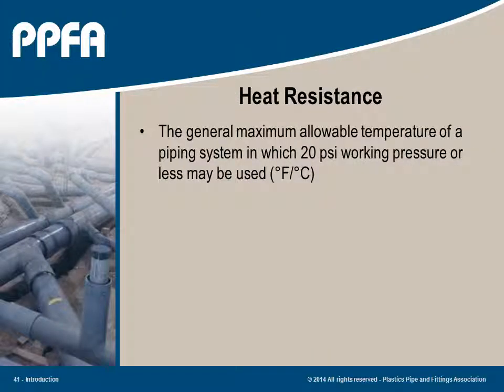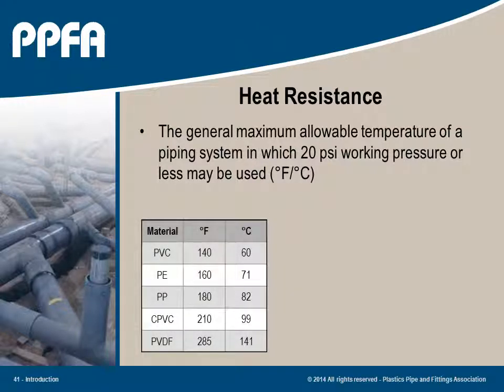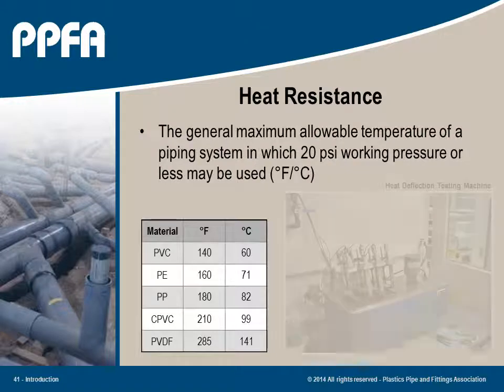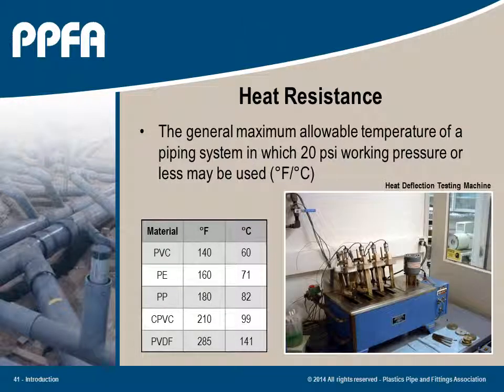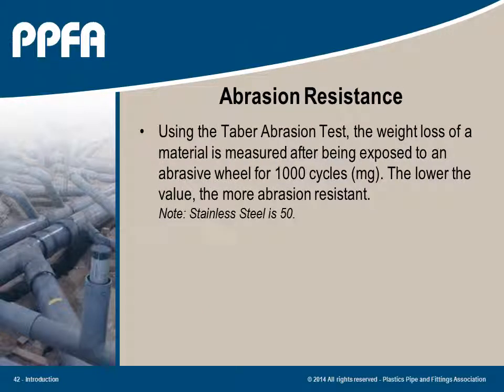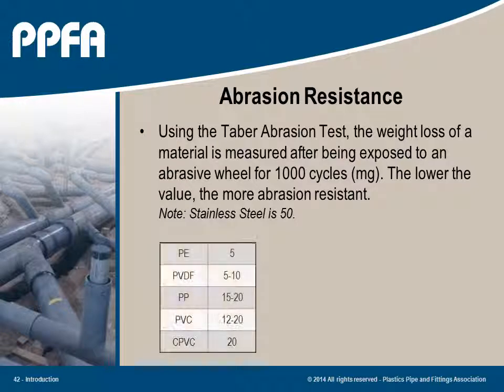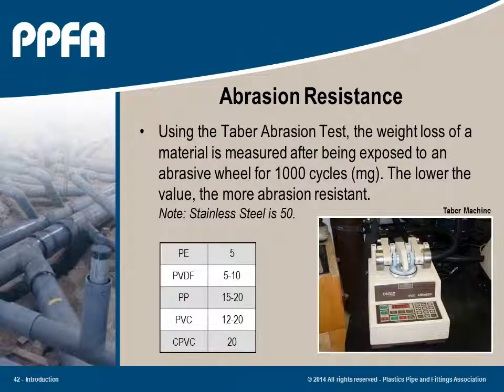The tensile strength and pressure ratings of thermoplastic piping decrease with an increase in temperature. These pressure-temperature relationships are calculated and listed in engineering tables. Most thermoplastic piping materials have an ability to resist abrasion and erosion much greater than most other non-plastic piping systems.